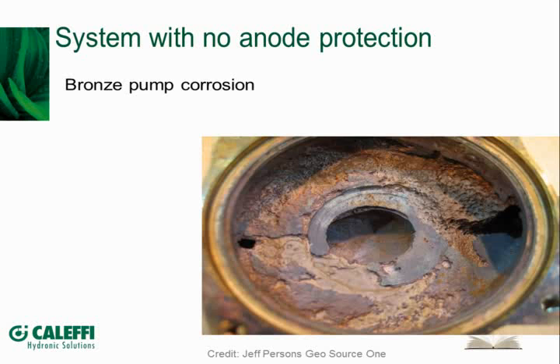Oh, and this is a great example. There may be some people listening in who have incredibly soft water — water that still stays slippery after your shower, so you can't get the soap off, it's so soft. This happens to be a bronze body circulating pump from a system with very soft water. It was on a hot water recirculation circuit, and the home had a stainless hot water tank and a stainless preheat tank, because they knew they had some corrosive issues with the water in the area, and thought using stainless would help them avoid problems with replacing water heaters repeatedly.